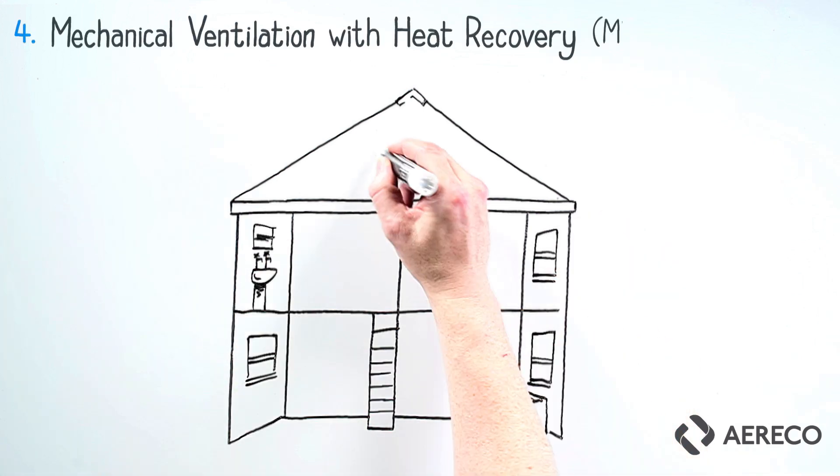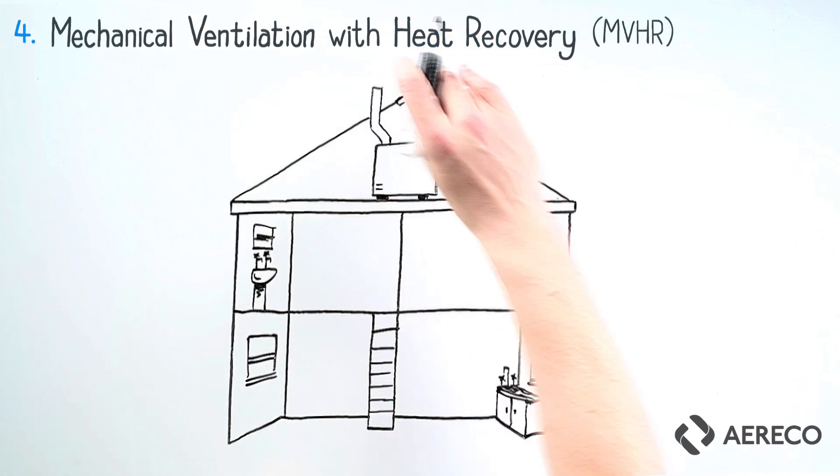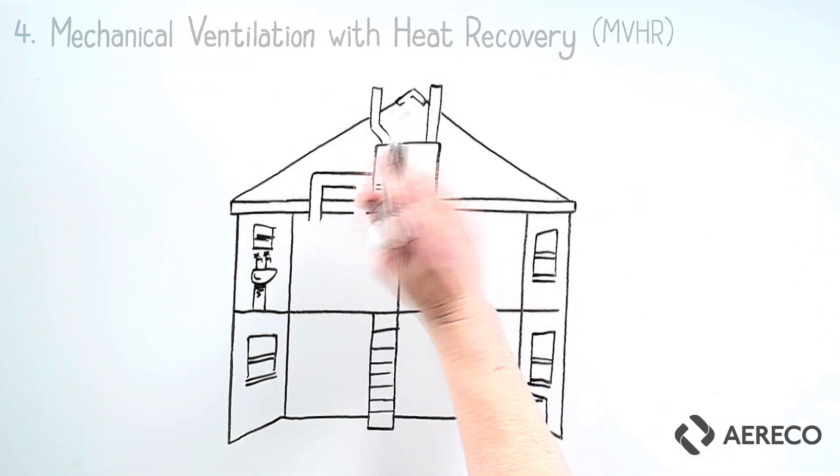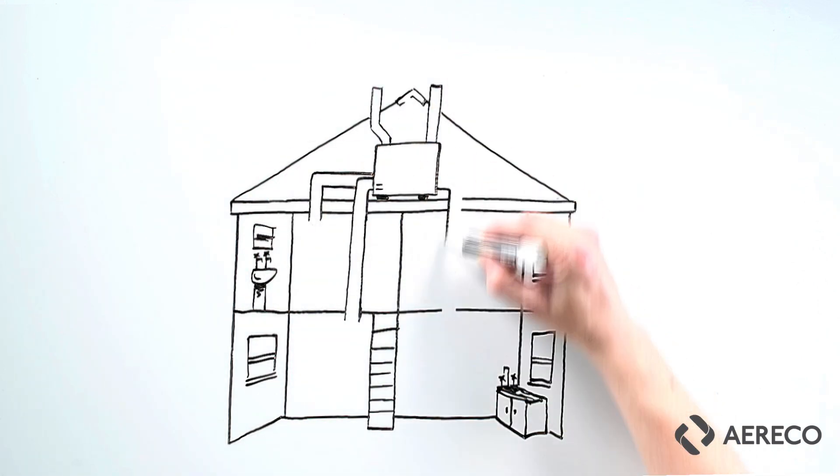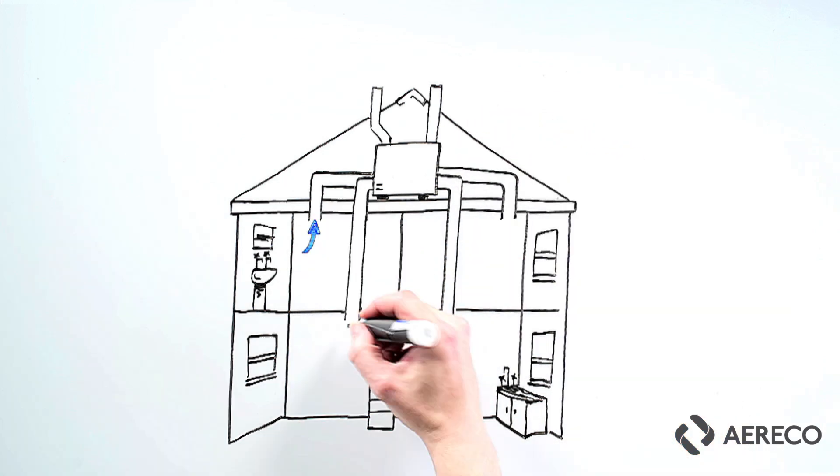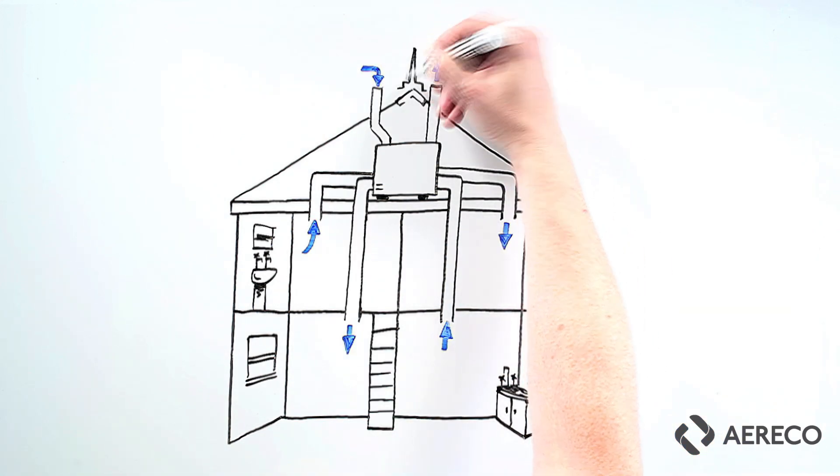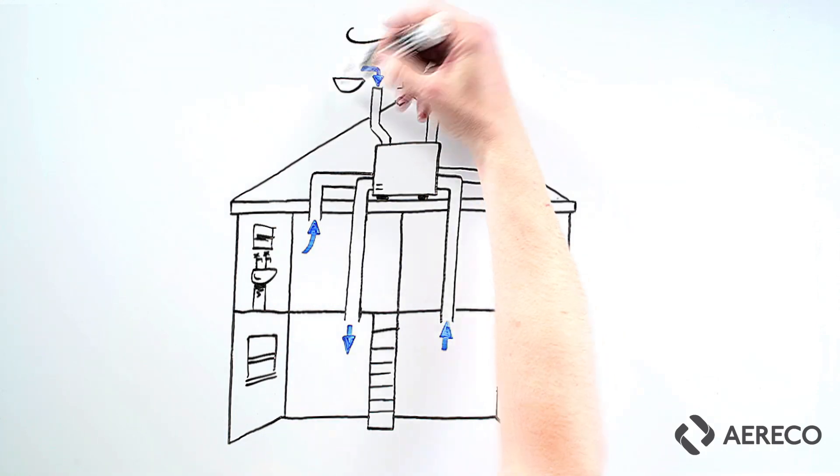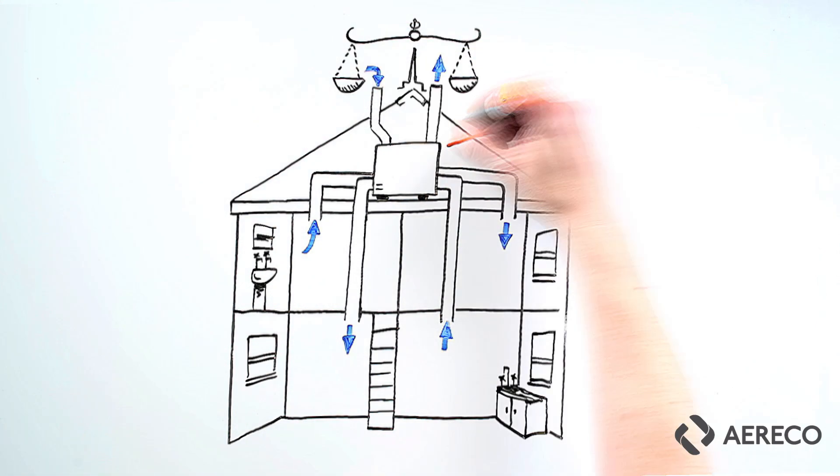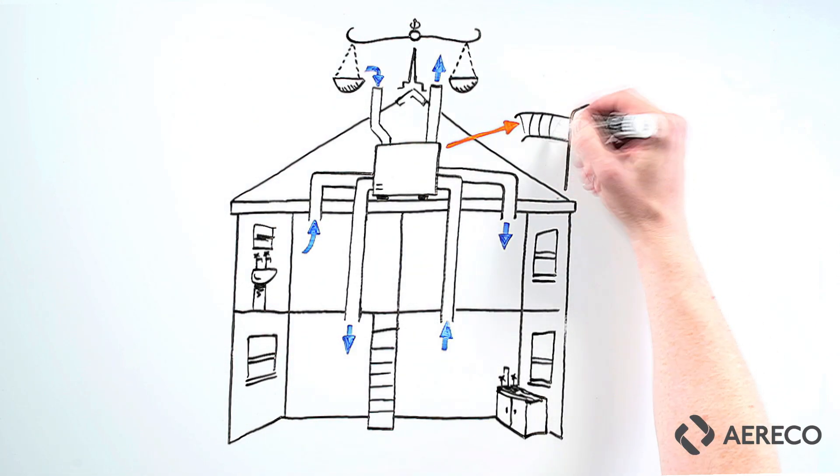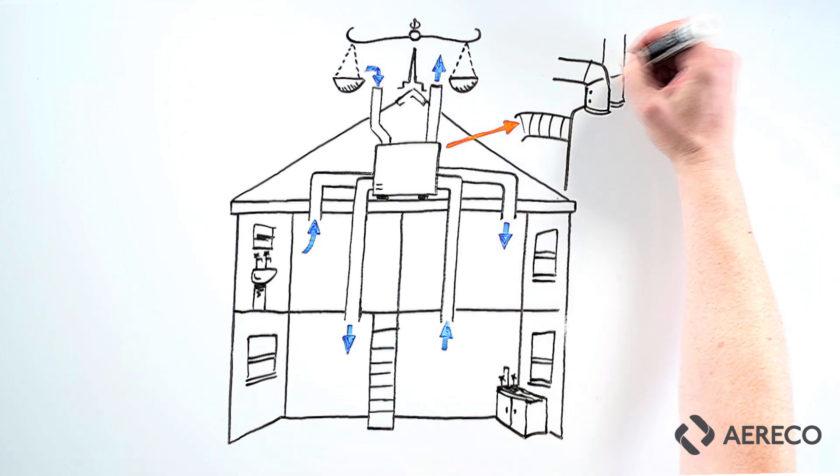Four: mechanical ventilation with heat recovery, or MVHR. An MVHR system is typically a large centralized unit that both extracts from the wet areas and supplies fresh air to the rest of the building via a series of ducts. Because the system is designed to supply as much air as it takes out, it's called a balanced system.